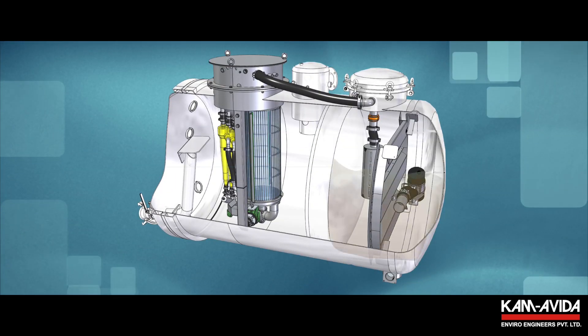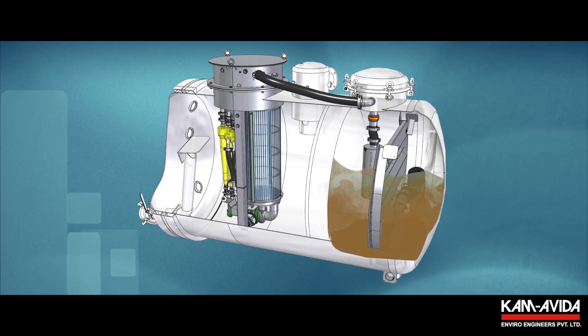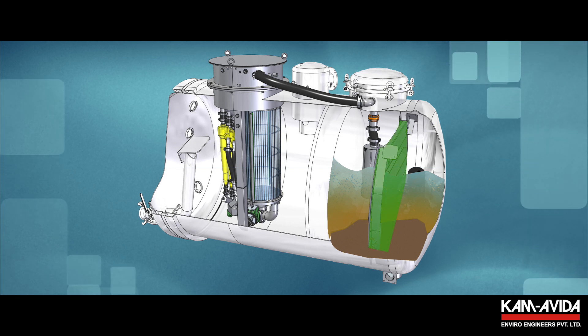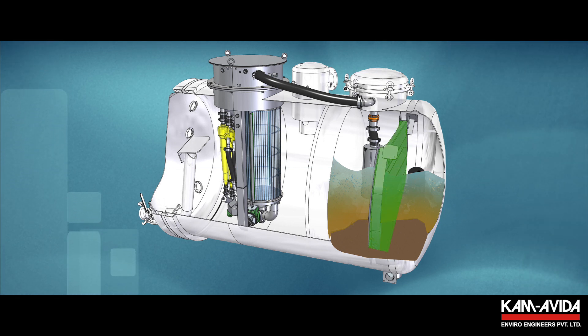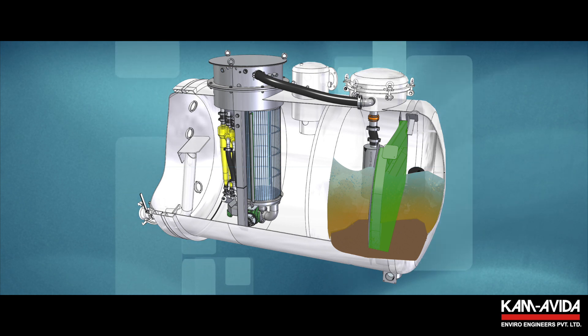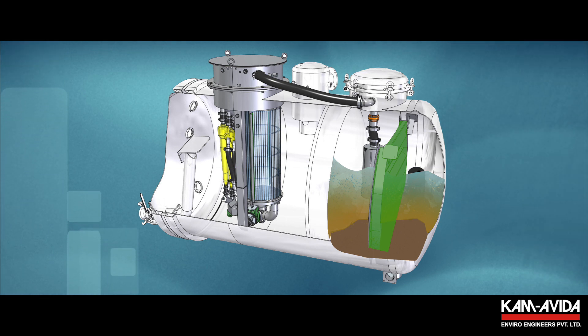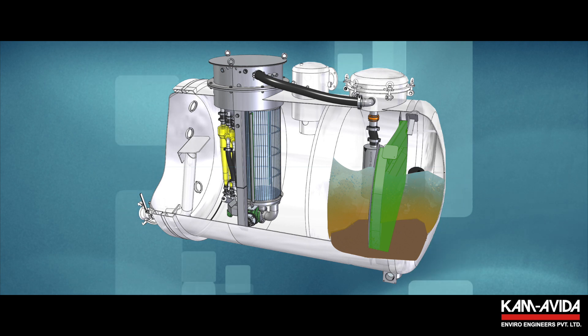The heavy particles settle to the rear of the tank, allowing the rest of the slurry mixture to pass through the first separation stage, consisting of an anti-sloshing wall or flip wall, which is positioned so as not to allow bigger particles to come in contact with the second stage filter. The second stage filter unit is designed to be installed inside the tank without affecting the overall size of the equipment.